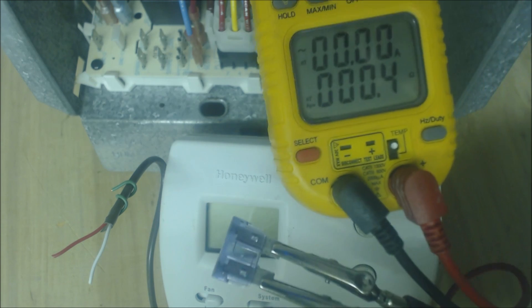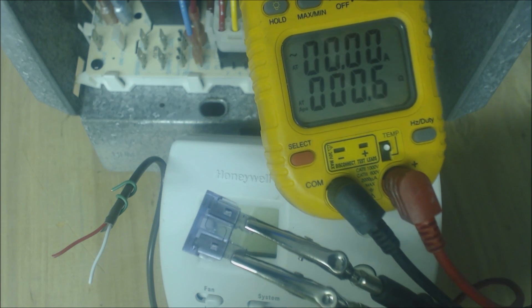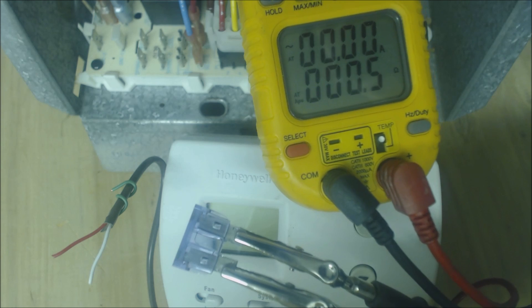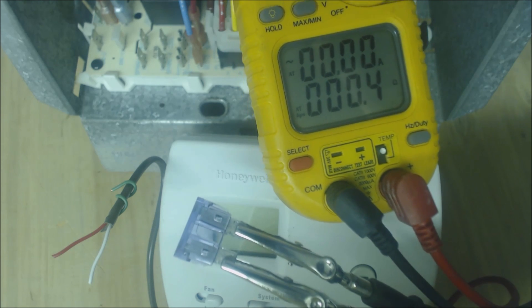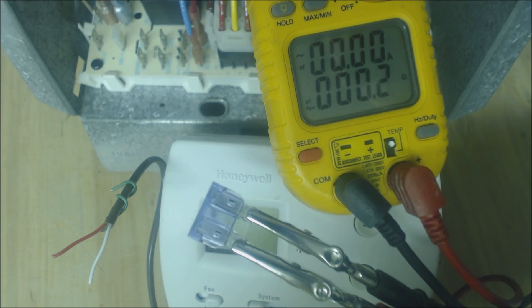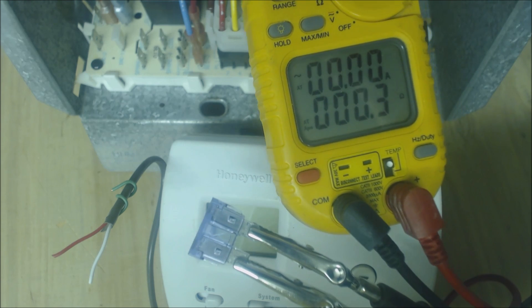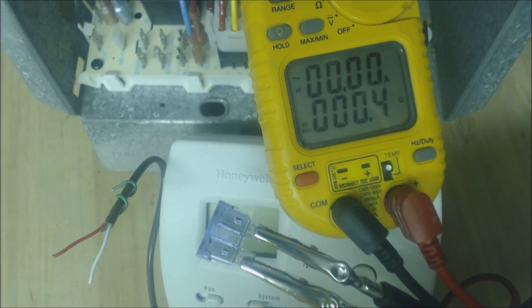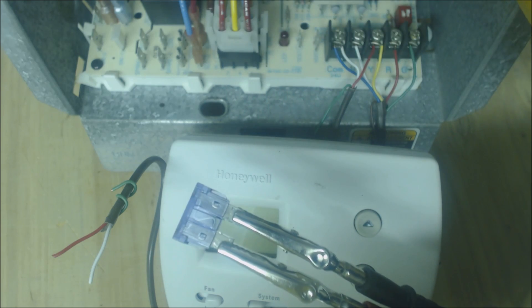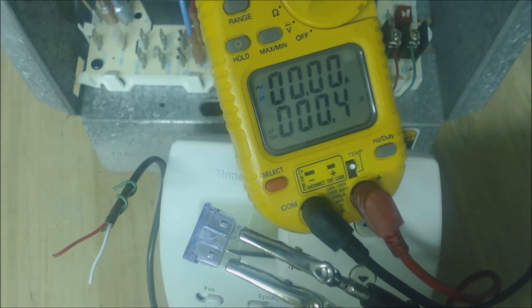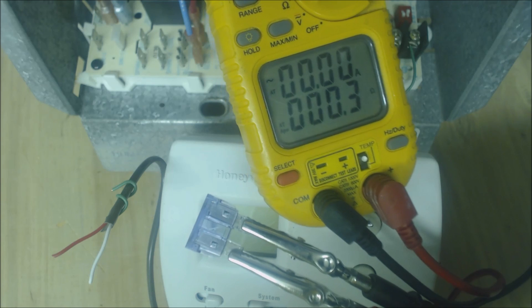Here's a good fuse—it's indicated by a very low resistance reading. In fact, it should be 0.0 ohms of resistance, but basically you should have very little resistance value. The only reason that this is reading resistance right now is because these alligator clamps are not biting into the surface of the metal. So this fuse would normally read 0 ohms of resistance to electrical flow.